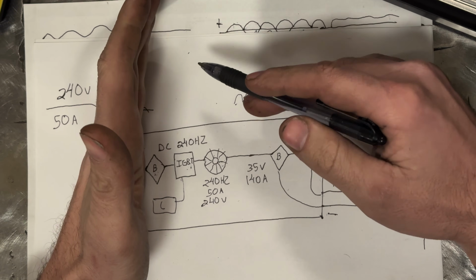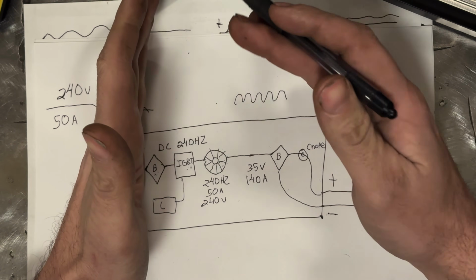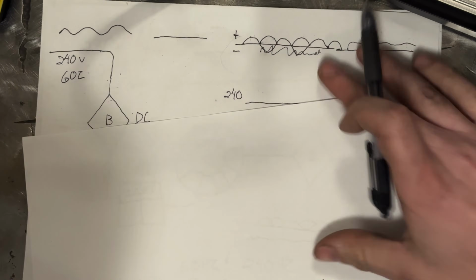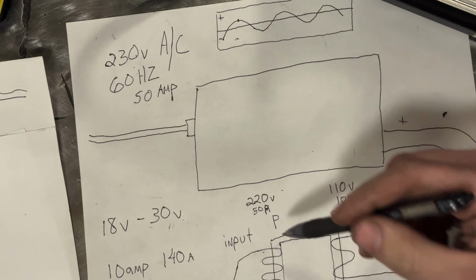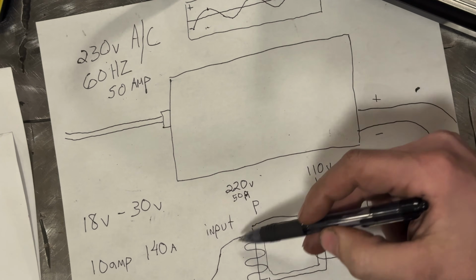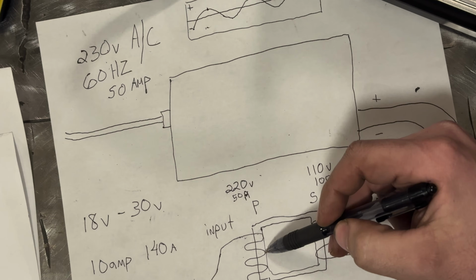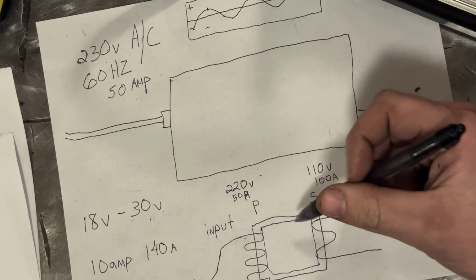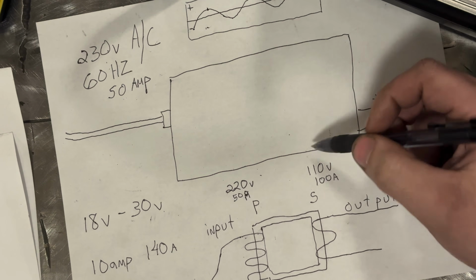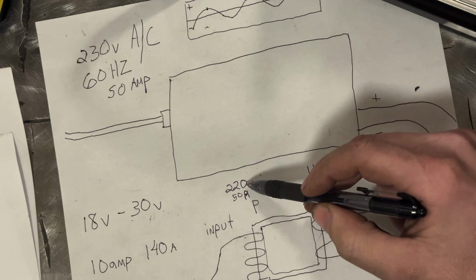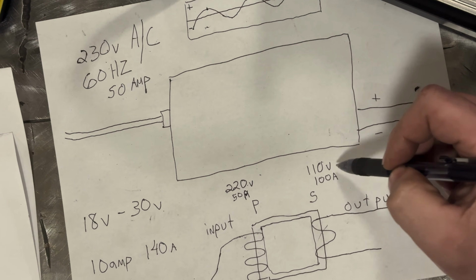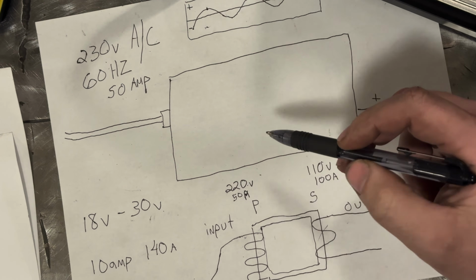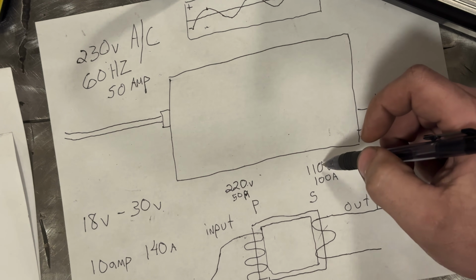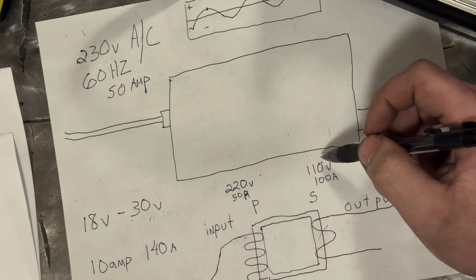And by manipulating the primary side voltage versus the secondary, it will change the secondary output. Like if we look here, going back to this, if rather than putting 220 volts in we put 110 volts in, that will half our output. So in this theoretical transformer, if we're putting 220 in and getting 110 volt out, if we put 110 in, we would get - what would that be - 55 volt out.